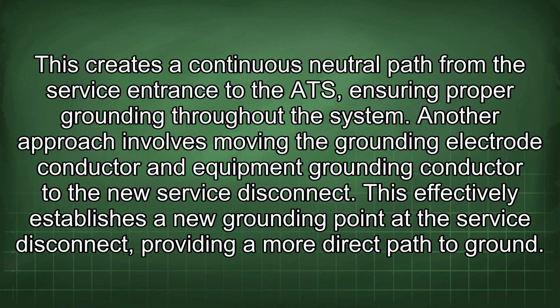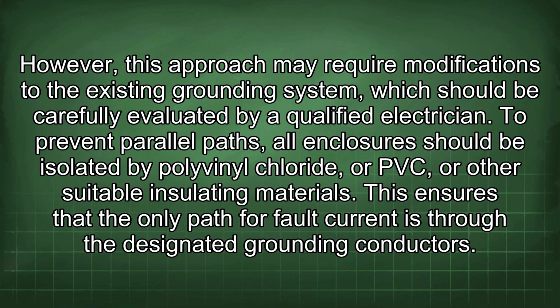This creates a continuous neutral path from the service entrance to the ATS, ensuring proper grounding throughout the system. Another approach involves moving the grounding electrode conductor and equipment grounding conductor to the new service disconnect. This effectively establishes a new grounding point at the service disconnect, providing a more direct path to ground. However, this approach may require modifications to the existing grounding system, which should be carefully evaluated by a qualified electrician.